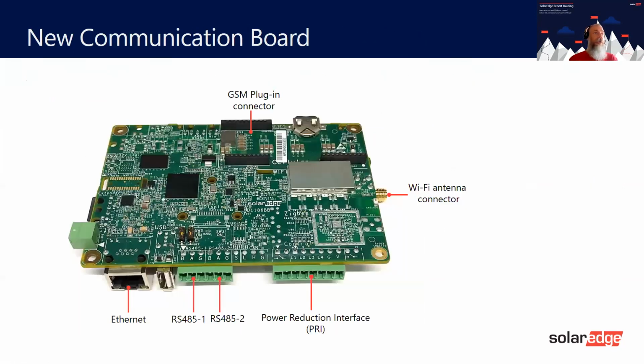And we'll look at the communication board. So this is the new communication board, and we'll start from 12 o'clock. This is where you would put the GSM or the smart energy plug-in in this area here. GSM is cellular, depending if we're in North America or not. Then we have the Wi-Fi connector. So if you want to use Wi-Fi to connect, simply connect the antenna onto here. You don't need to have an antenna when you're doing the setup process. You'll be able to get at least 6 meters range from the inverter as it is. This is your power reduction interface that works with the RRCR, that allows you to control the inverter remotely from 100% down to 60%, down to 30% or to 0.